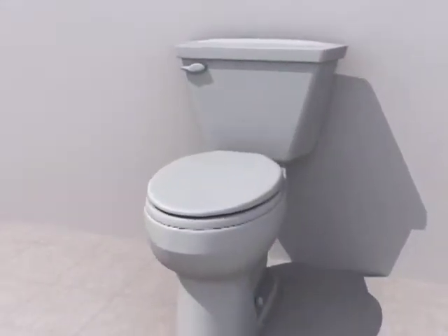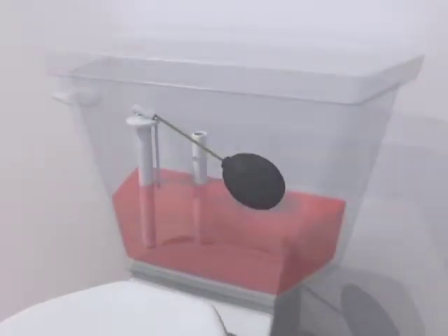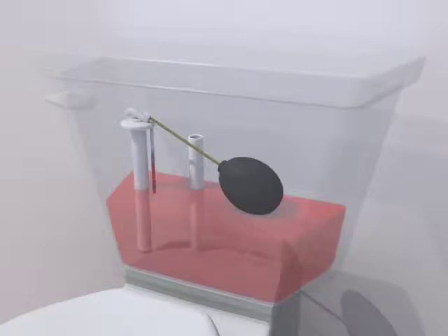Okay, now that you know what cross-connection and backflow are, you need to know what you can do to prevent contamination due to cross-connections and backflow. To solve this problem, we actually control the backflow part of the equation. You see, cross-connections are actually part of our plumbing and water systems, and we simply can't eliminate them altogether. For example, the average toilet has a cross-connection. As you can see from this diagram, the potable water enters the toilet tank, and if backflow were to happen, the non-potable tank water could flow back into the potable water through the cross-connection.